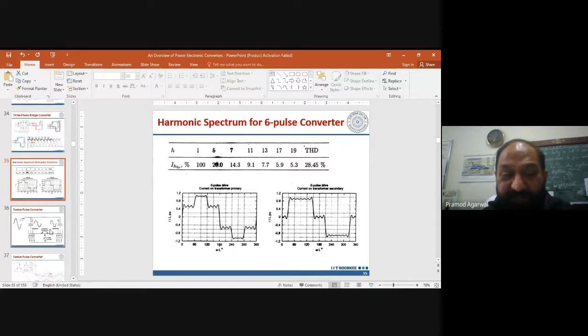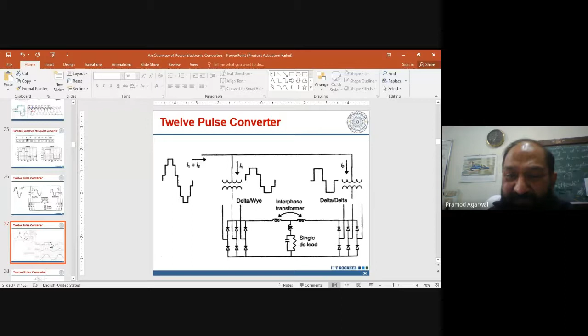And you can go from 6 pulse to 12 pulse. And in this case, what is done? There are two converters which are 6 pulse converters. They are connected either in parallel, but one converter is fed through delta Y, another is fed through delta delta. Or you may connect them in series. So star star, star delta. The point is that one of the secondaries is the same as the primary. If this is star, this is also star. Another secondary is different.